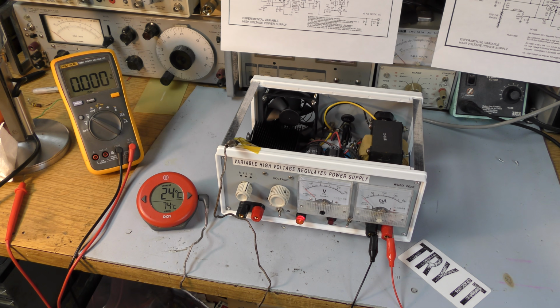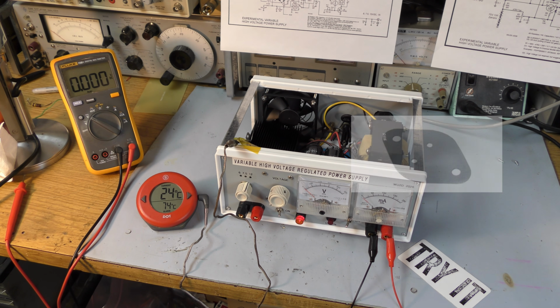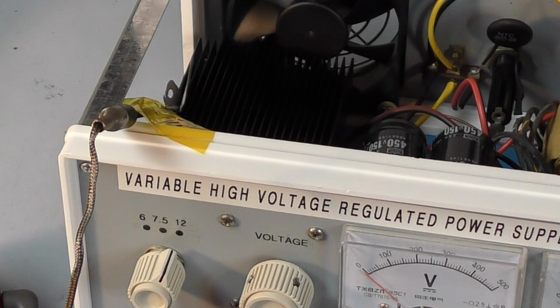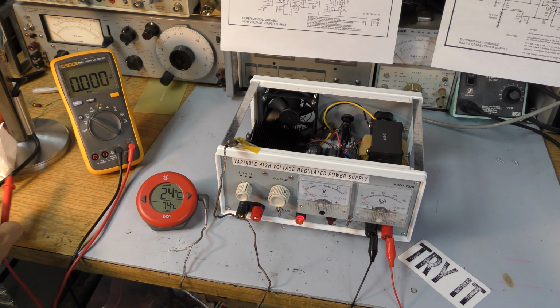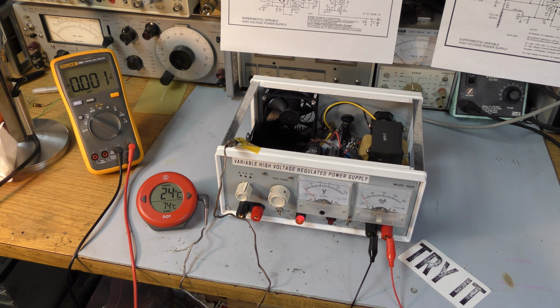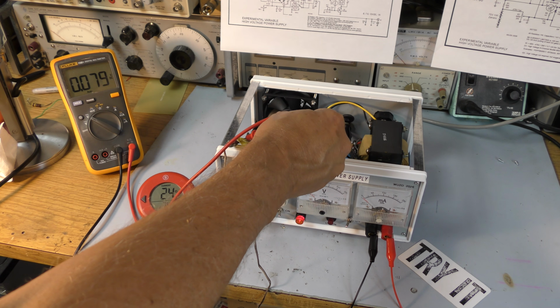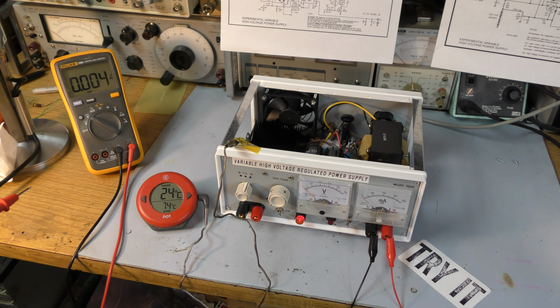Okay, I have the temperature sensor connected, and I've taken some precautions to make sure the probe is not at 600 volts. Not trusting the anodize of the heatsink, I used one of those old-fashioned TO3 insulators, wrapped it around the tip, and jammed it in between one of the fins near the temp sensor. It's on right now, so let's touch the voltage probe and verify there's 0 volts on it. Okay, so we are insulated.